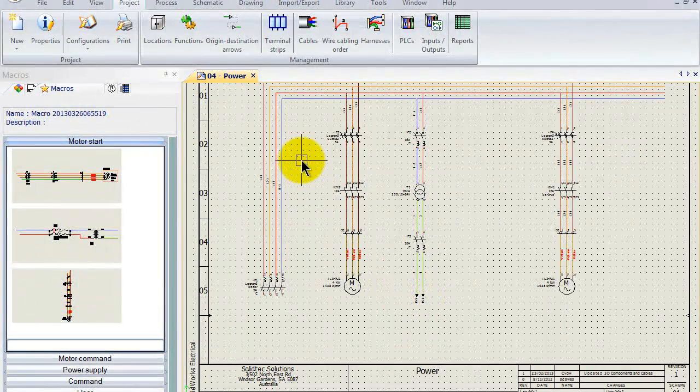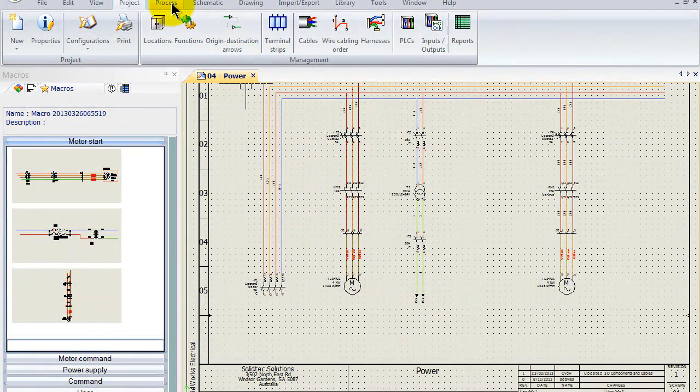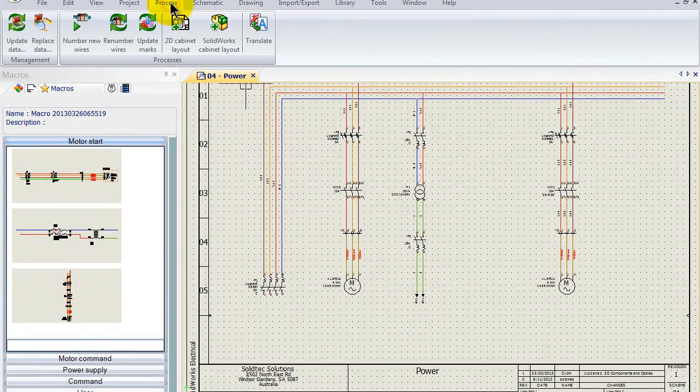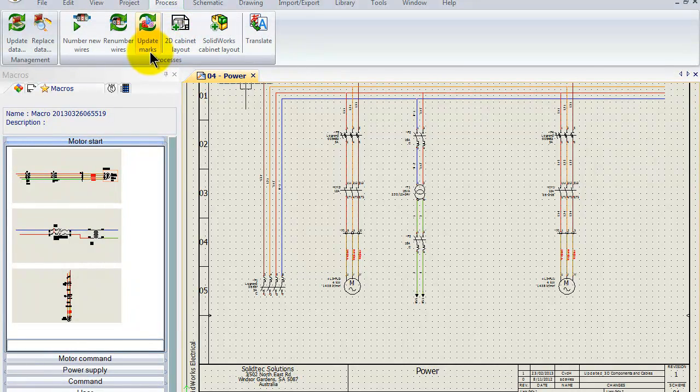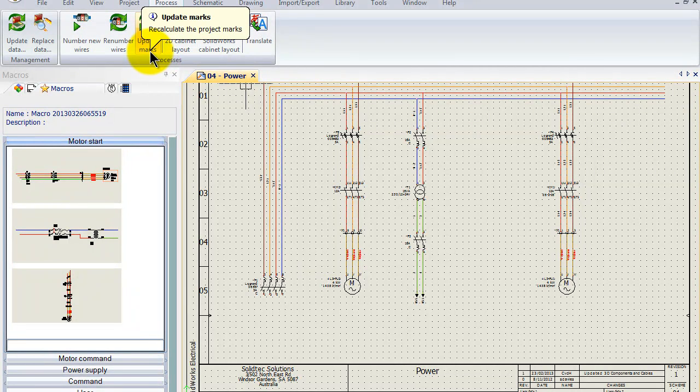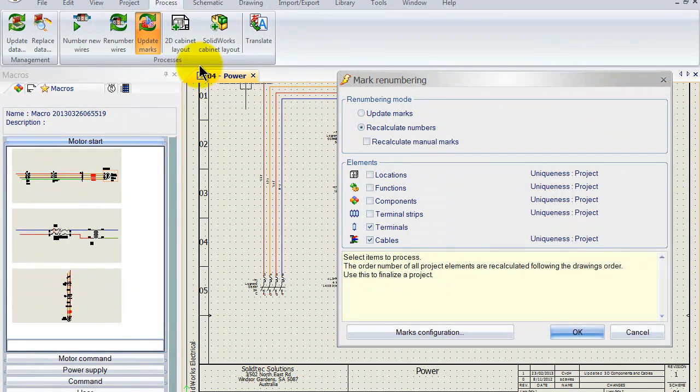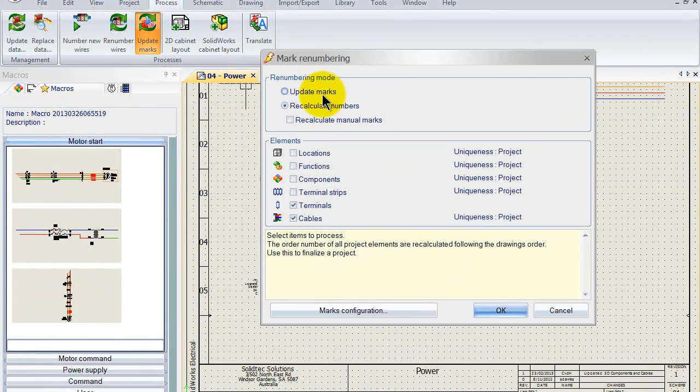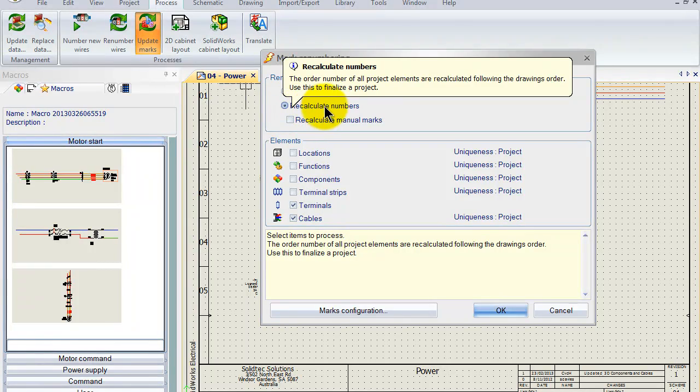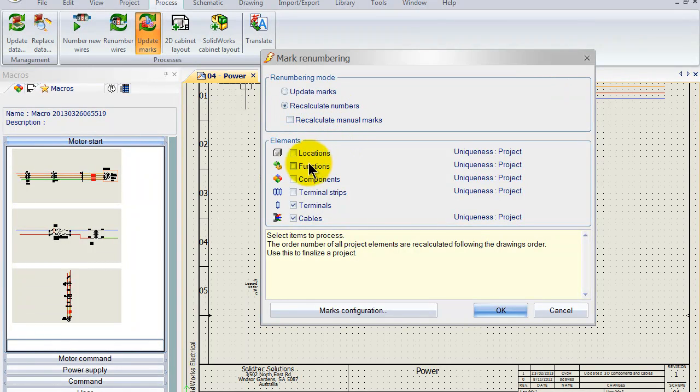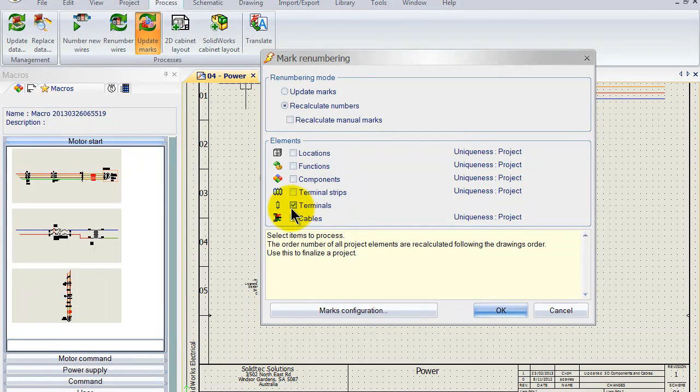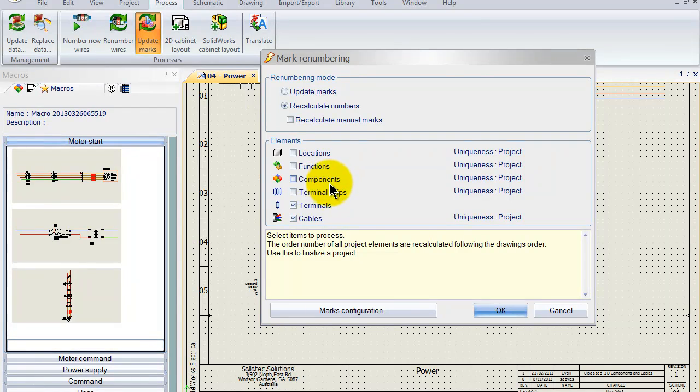Now what we can do is we can go to the process tab up here and we can select the button update marks. That will actually recalculate all the project marks. Now project marks, we can update them or we can actually recalculate all of them. We can select the ones that we want to use. Now in this case I want to renumber terminals and cables, but of course you can also do the same thing with component marks and the actual terminal strips itself.